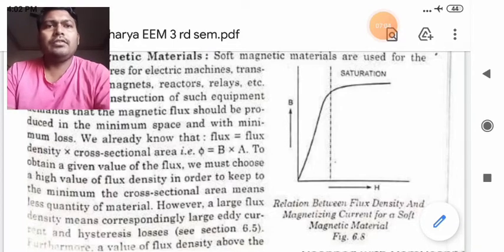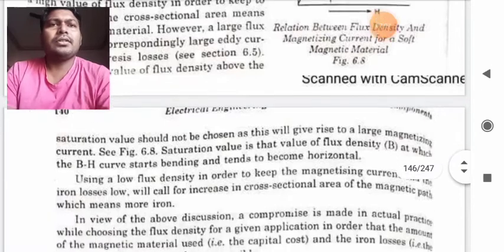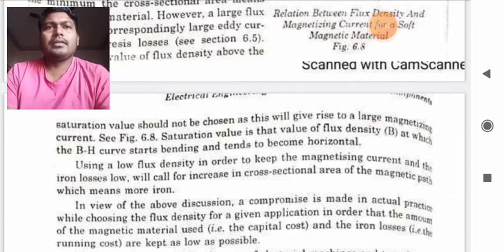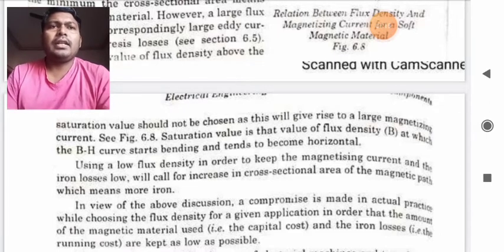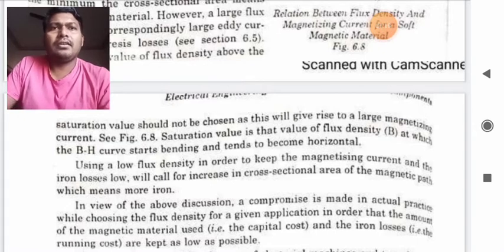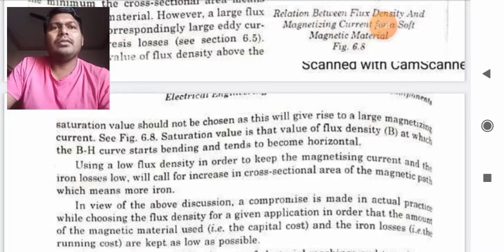Furthermore, a value of flux density above the saturation should not be chosen as this will give rise to large magnetizing current. In the diagram, saturation value is that value of flux density at which BH curve starts bending and tends to become horizontal.